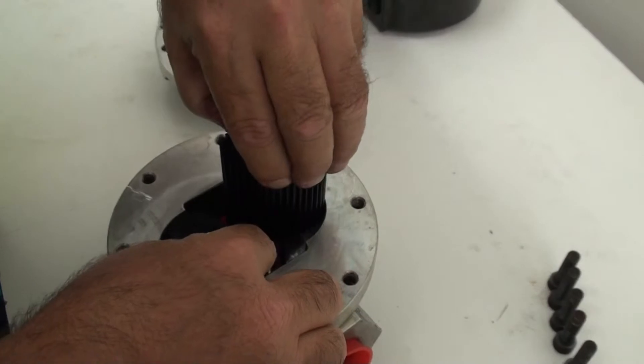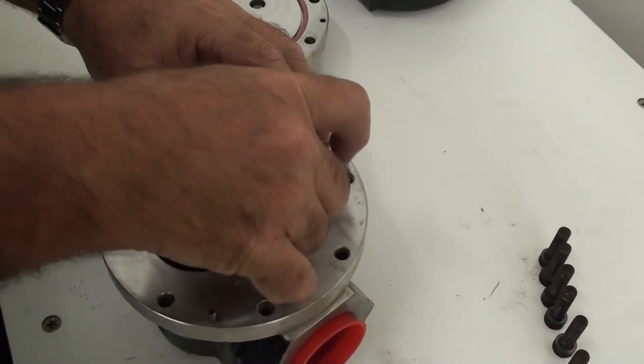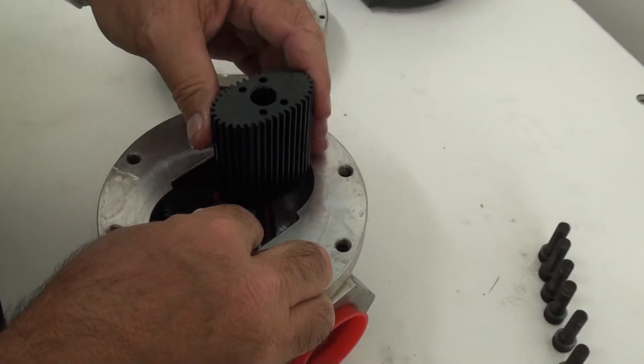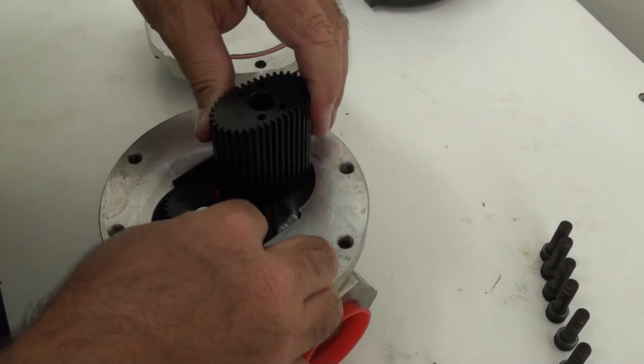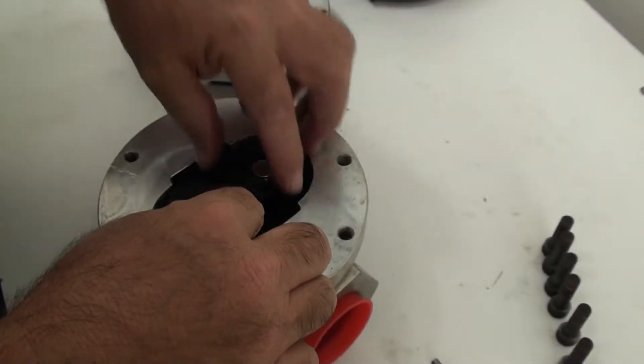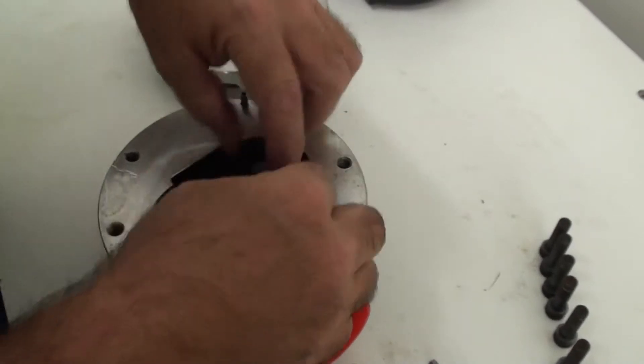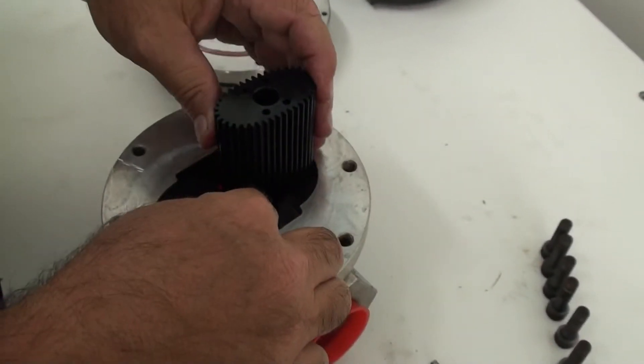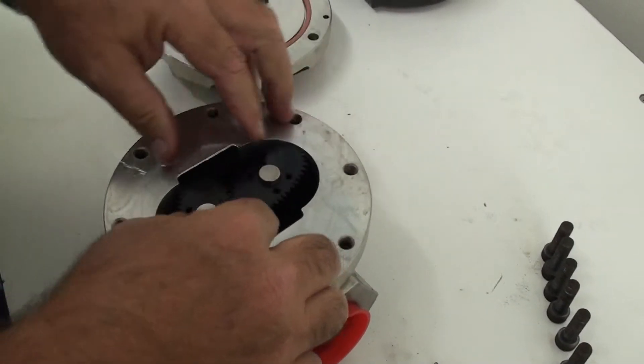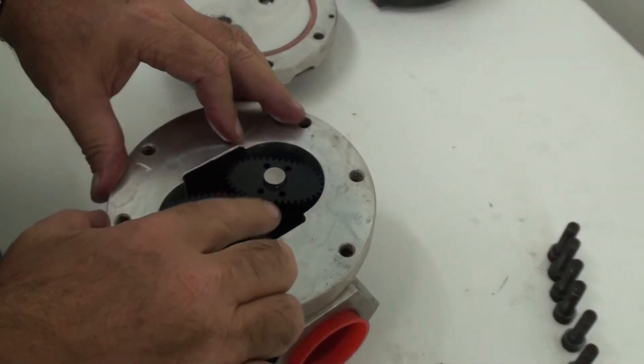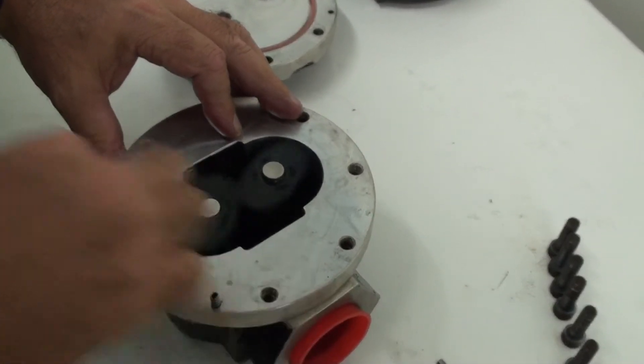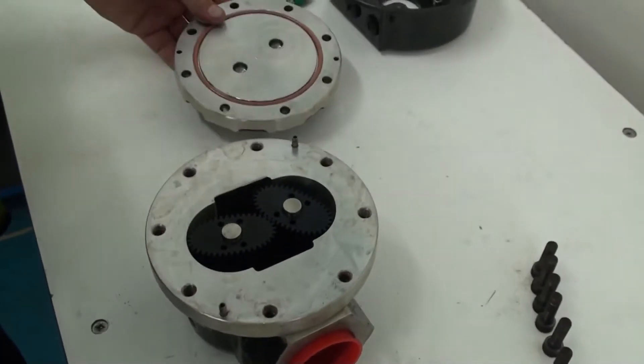And as you can see I'm struggling trying to get these rotors back in position. But it's very very important that they are in exactly the right position. And it's just a matter of moving them across one tooth. And as you can see when I get them in the right position they turn quite freely. But I know that it's right.